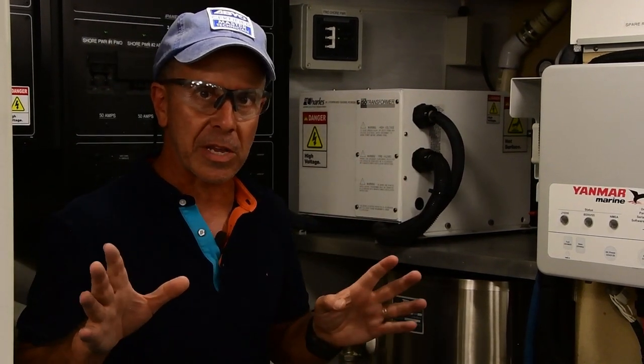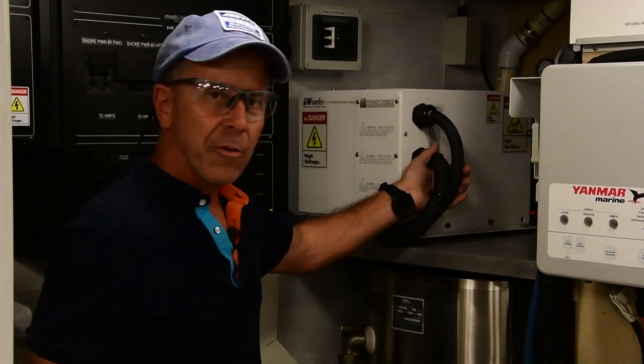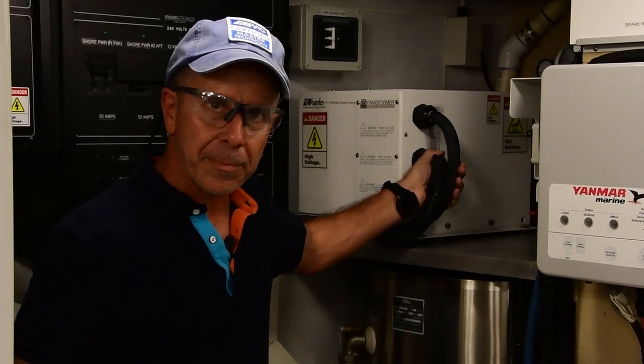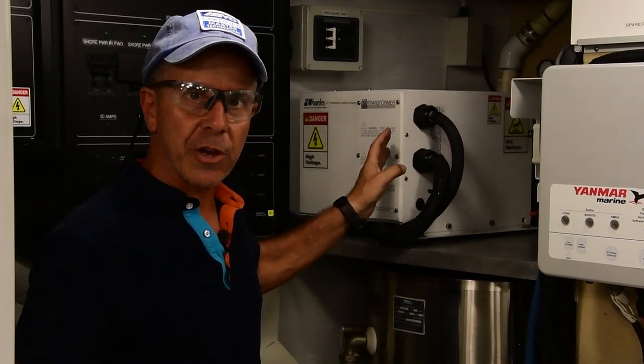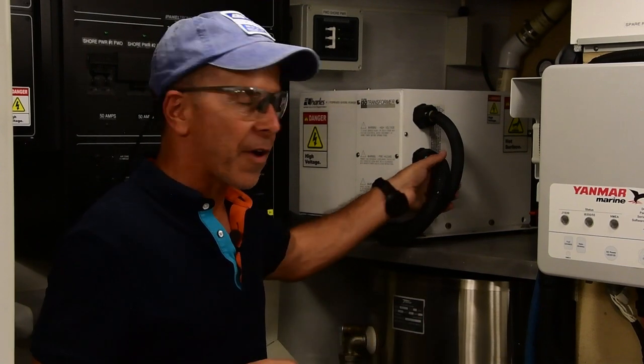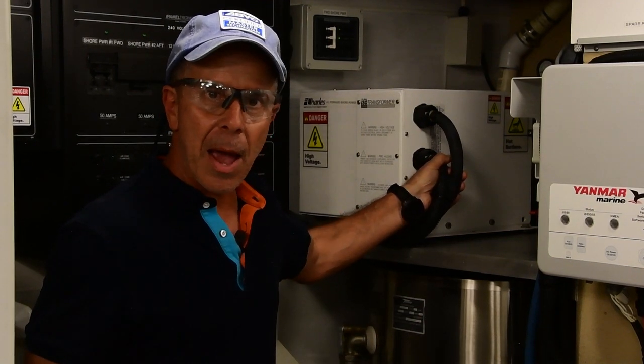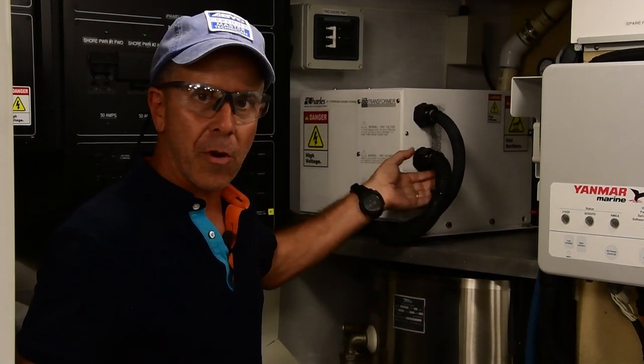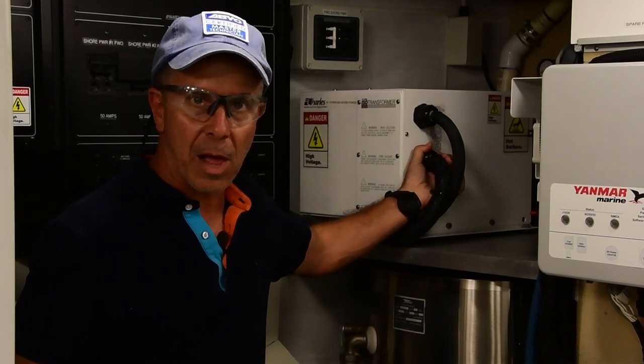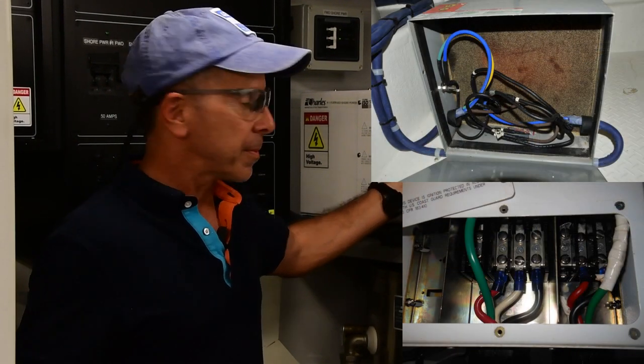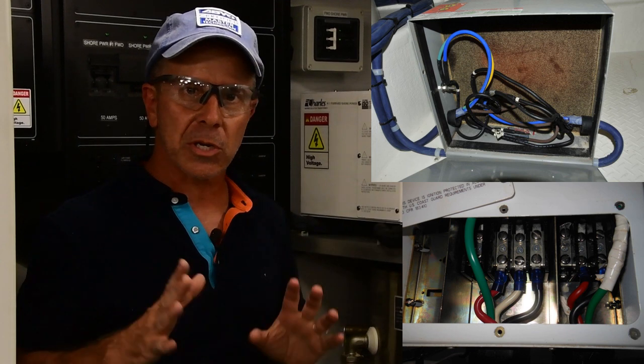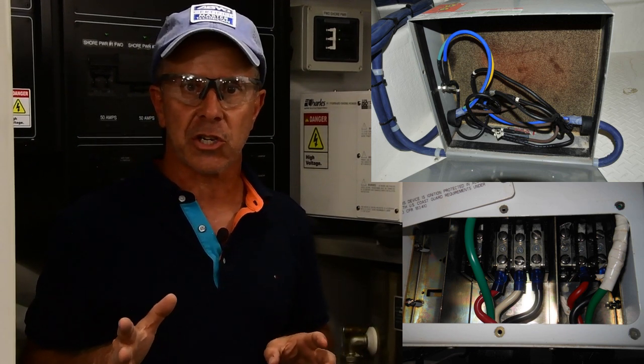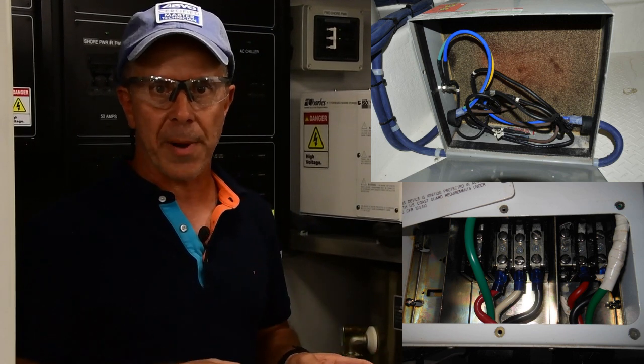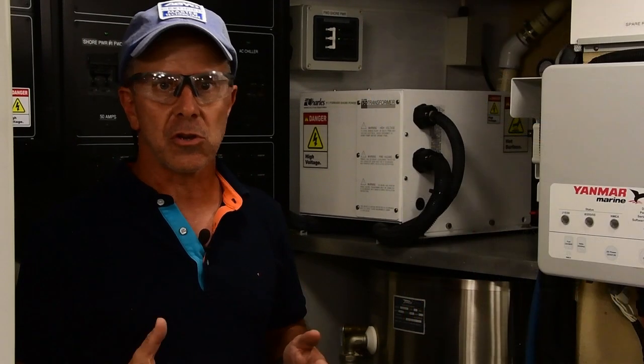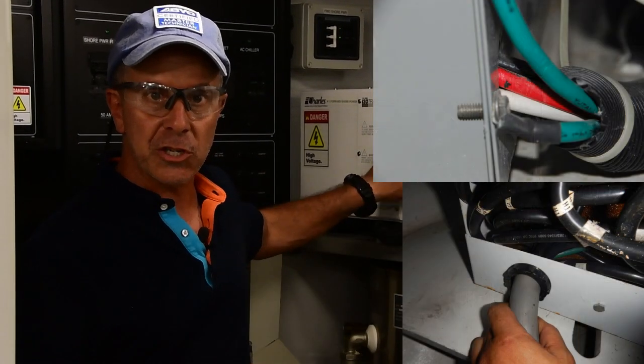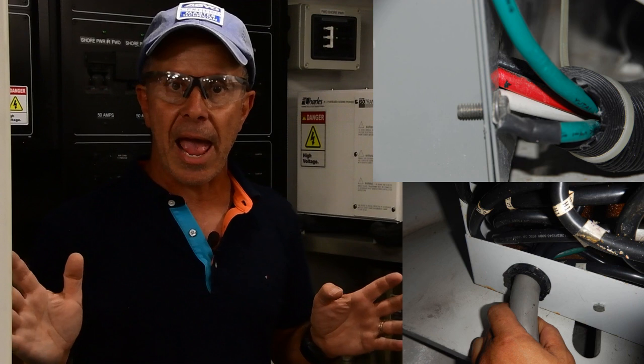But what else does this cord grip do? Well, the name is a little bit of a giveaway. The grip prevents the wires from moving inside the transformer where the connections are made. So if I pull on these wires, I'm not moving anything inside the transformer because they're completely immobilized at this cord grip. This is probably the most commonly violated installation guideline for shore power transformers: failure to use a cord grip. You may see chafe protection, but that's only half the battle.